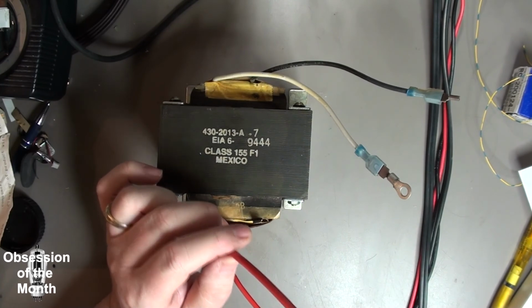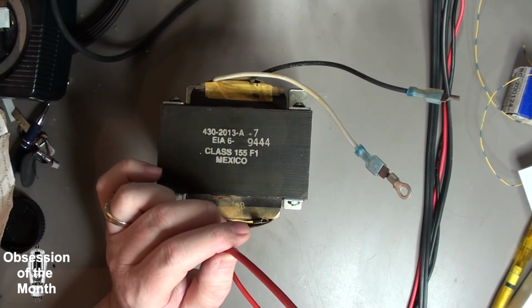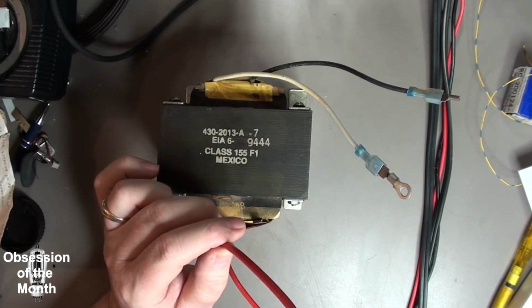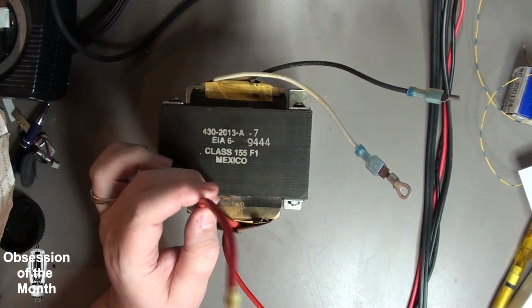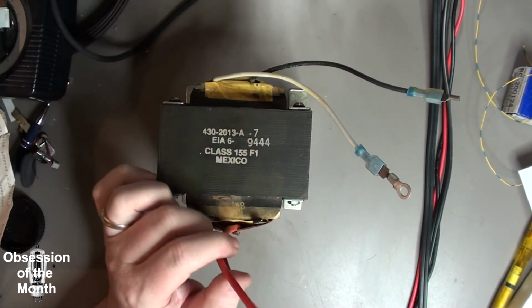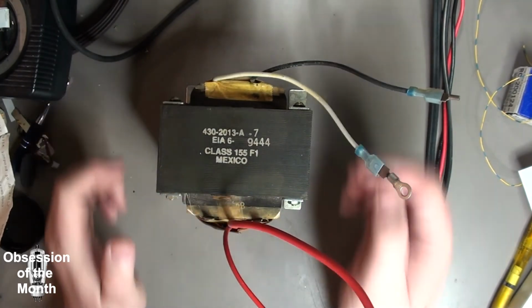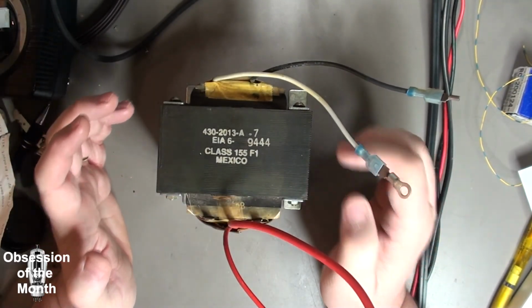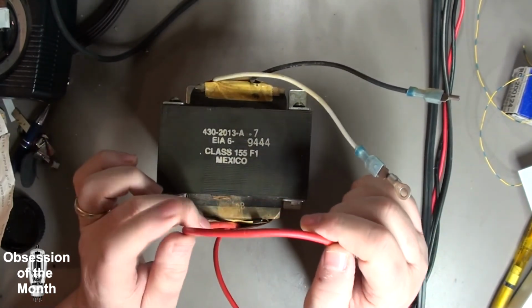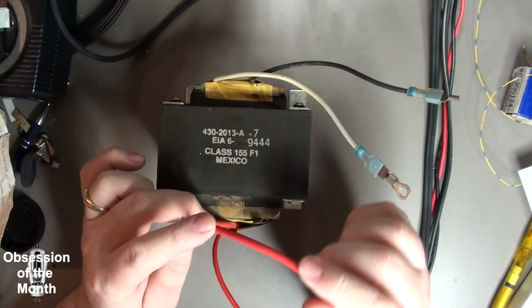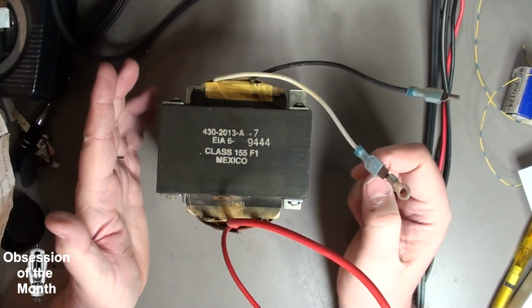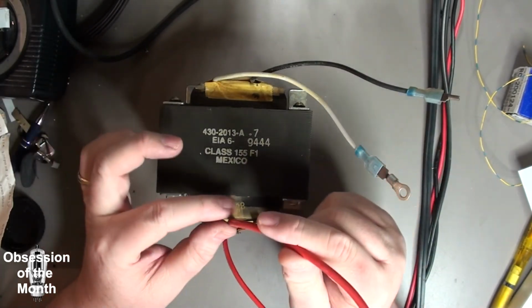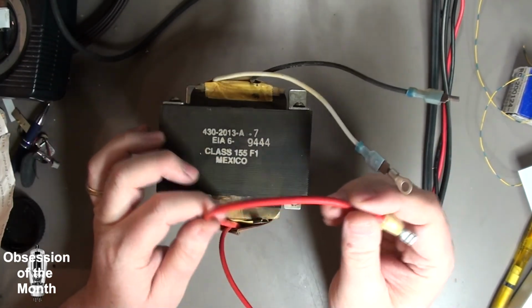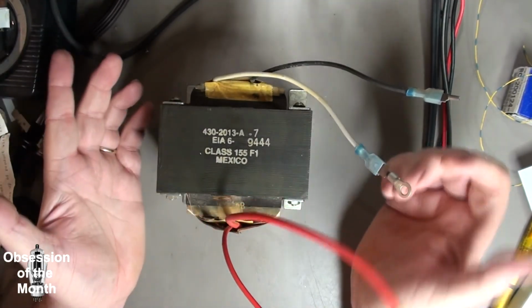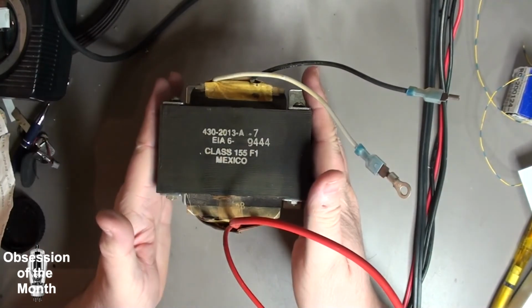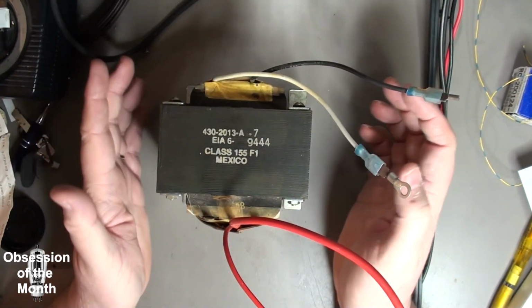If you go with ampacity ratings based on house wiring, for 10 gauge wire you're looking at about 30 amps. That gives you a basic idea of the maximum amps you can pull. You never want to go to the maximum, but if you need 10-15 amps and can get 30 amps out of this wire, that's less than half, so it'll have no problem running your battery charger and charging a battery.